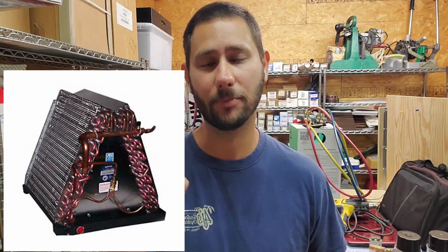Before we talk about the top causes for your air conditioning system to freeze during the summer, we need to know how the unit operates so that we can better understand where it freezes first. You have an inside and an outside coil. Whether you have a split system where you have two pieces of equipment or one piece of equipment, you have two coils. One coil is called an indoor coil, which is an evaporator coil, and that's where it freezes first. You also have another coil called an outdoor coil, a condenser coil, and it rejects heat. So the evaporator coil that absorbs heat is where it's going to freeze first.